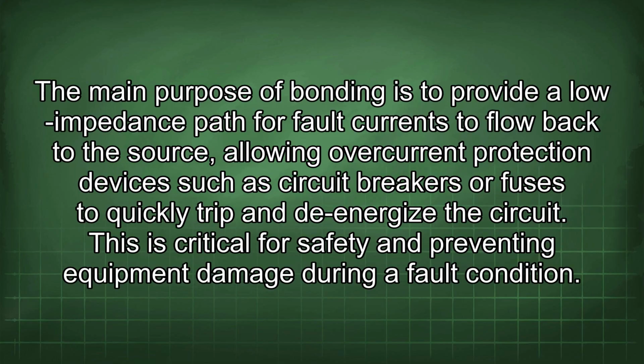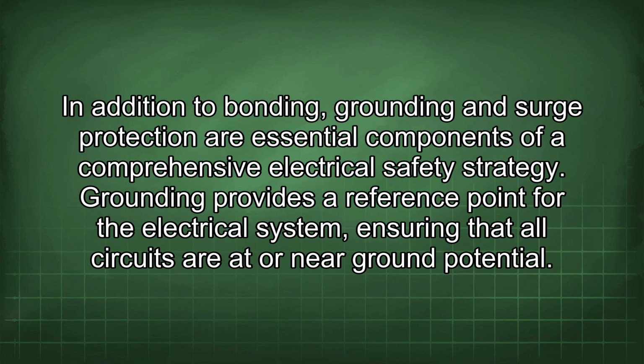The main purpose of bonding is to provide a low impedance path for fault currents to flow back to the source, allowing overcurrent protection devices such as circuit breakers or fuses to quickly trip and de-energize the circuit. This is critical for safety and preventing equipment damage during a fault condition. In addition to bonding, grounding and surge protection are essential components of a comprehensive electrical safety strategy.